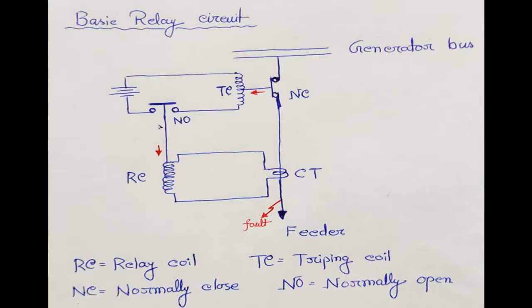So, as the plunger is moving in the downward direction, this normally open switch becomes closed. As the switch becomes closed, the tripping circuit is complete, and current flows from the battery to the tripping coil. The tripping coil is energized, and the coil attracts this plunger in that direction, shown by the red arrow.